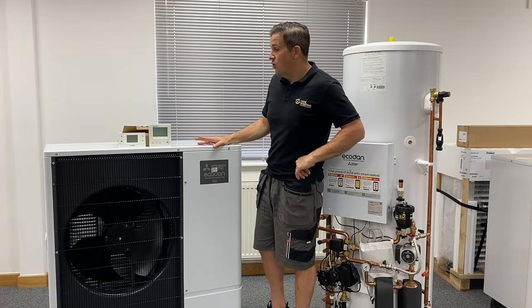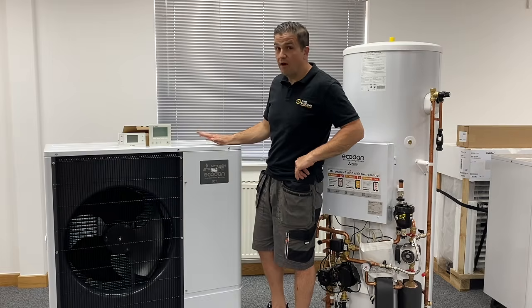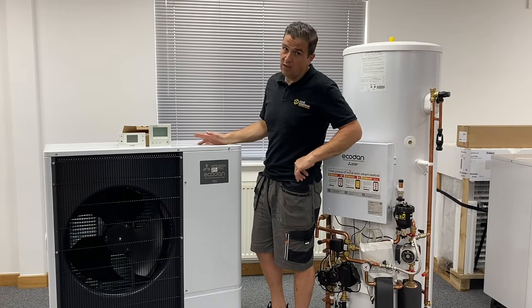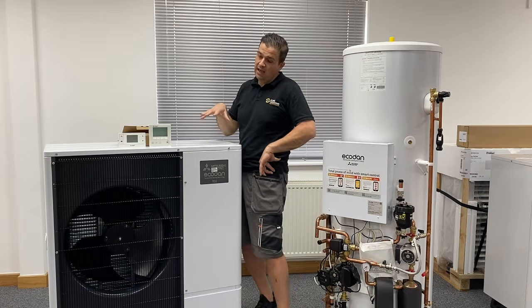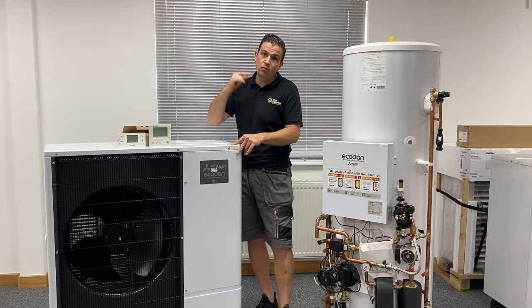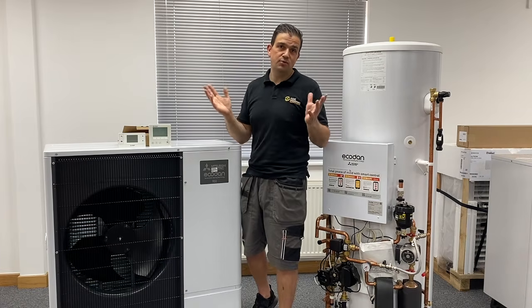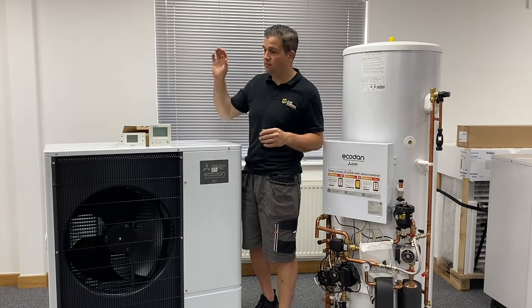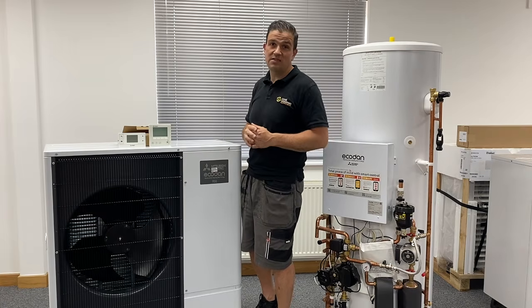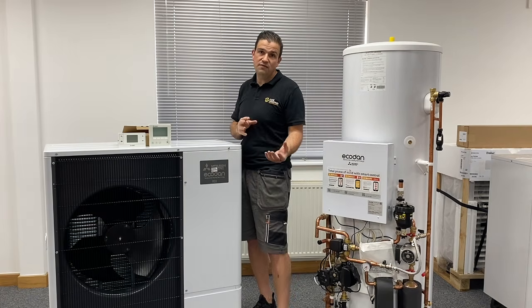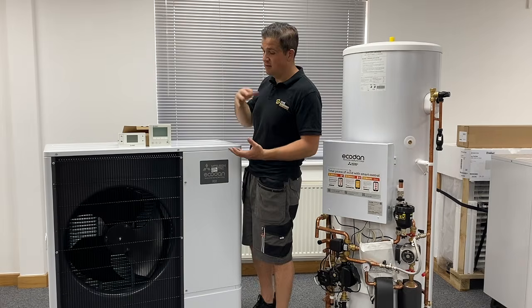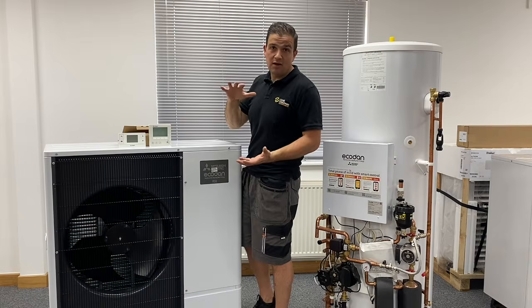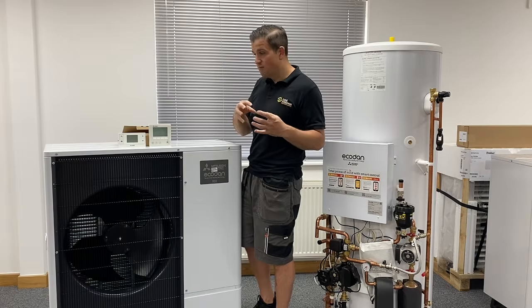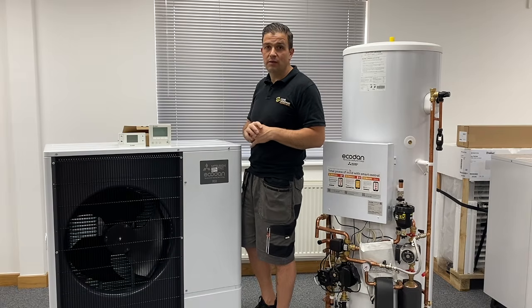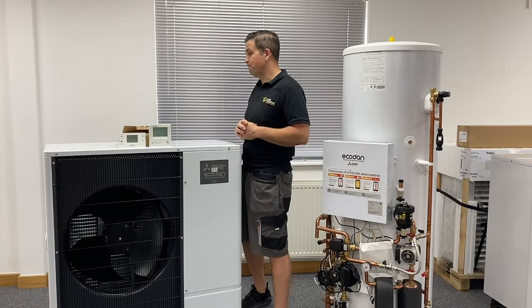The Ecodans also will come in several sizes. We get a 5 kilowatt, 6 kilowatt, 8.5 kilowatt, 11.2 kilowatt, all in a single fan unit. The only double fan unit is the 14 kilowatt Zubadan. So that's the biggest one that they do. It's a double fan. With that one, it's not under permitted development, so that would need to have an application for planning, because the capacity of the refrigerant and its ability to deliver heat is slightly on the larger scale. Therefore, it doesn't quite fit into the realms of permitted development for planning.